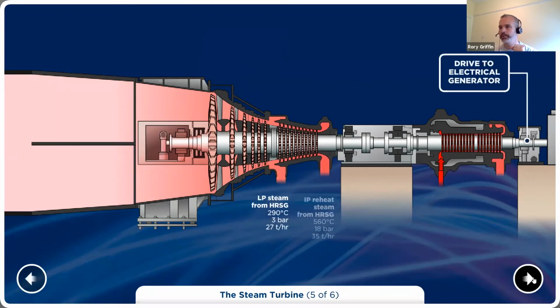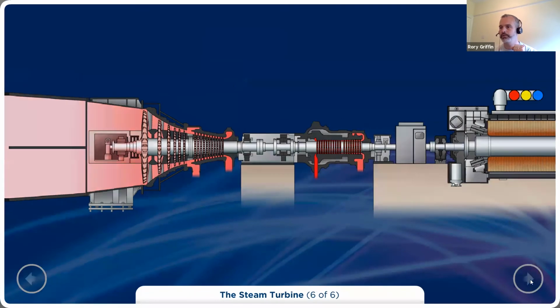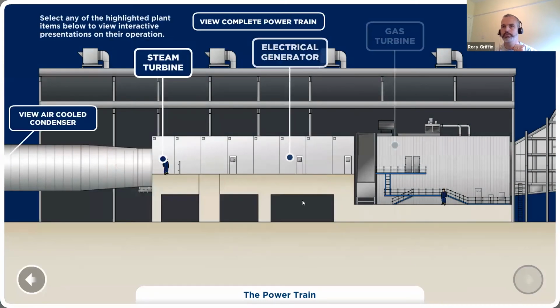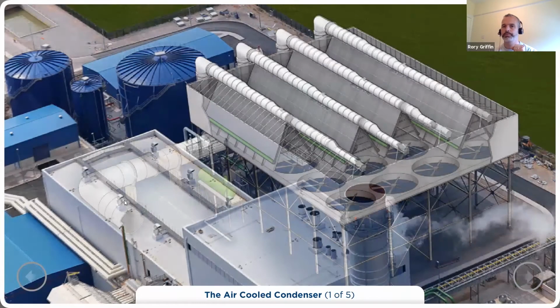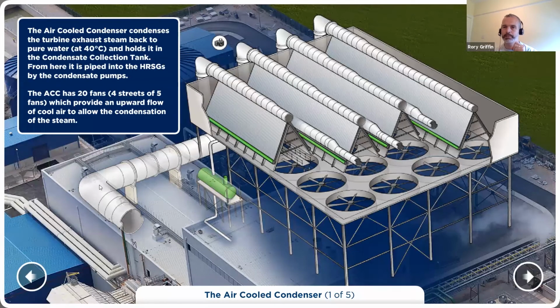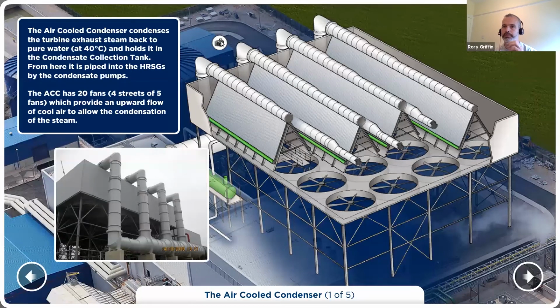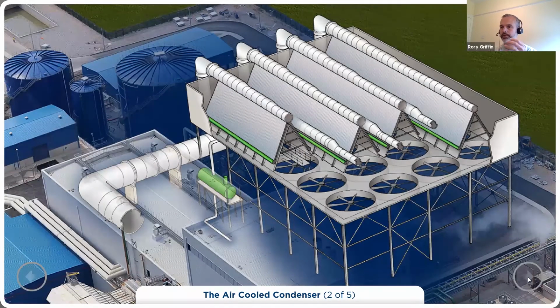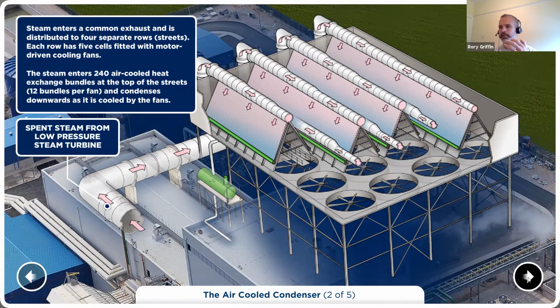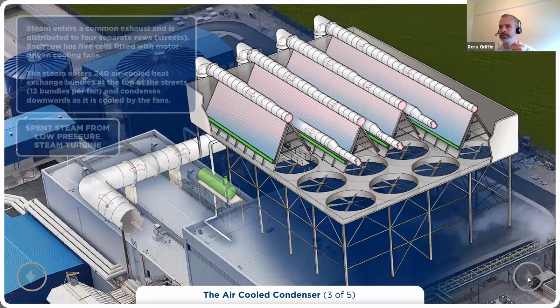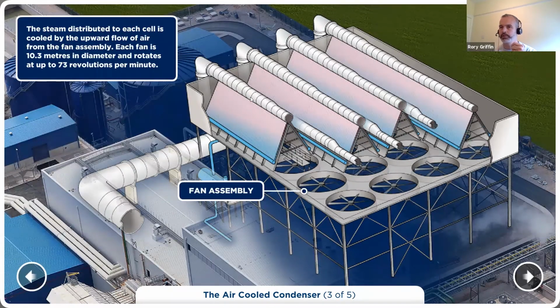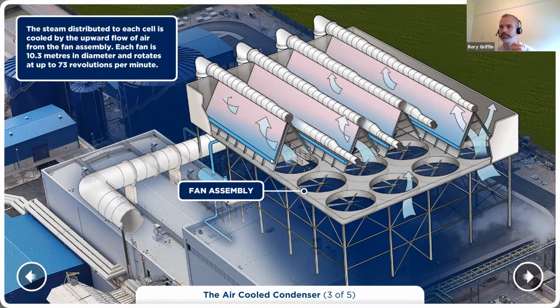I will just move out to the air-cooled condenser and just show you how we condense it back to water. So this is the back end of the steam turbine here. It'll come along this duct here, up these pipes here, up to the top header. And I'll just get the fans moving here. So this is our air-cooled condenser. There's 20 fans arranged in 4 streets. There's 5 fans per street. And what happens then is, once the steam comes along the top, it'll go down through these little tubes, and it collects here as condensate, and it'll feed into one pipe down into the condensate receiver tank here.